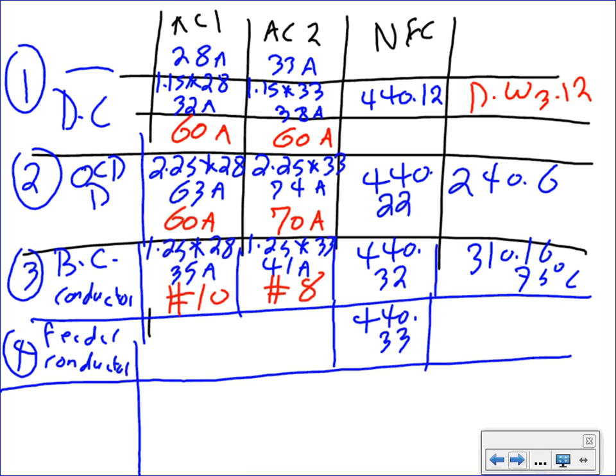Does that sound like motors? 1.25 times the largest motor. What's the largest motor? 33, plus all the others sharing the feeder, 28. What would that give you? Don't forget that you have to put the brackets here. First you multiply, then you add. Can't believe how many people add them and then multiply them.